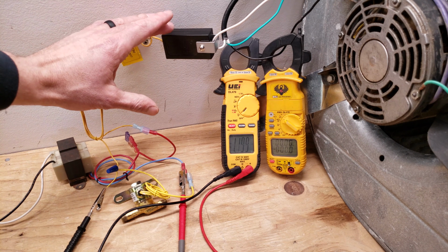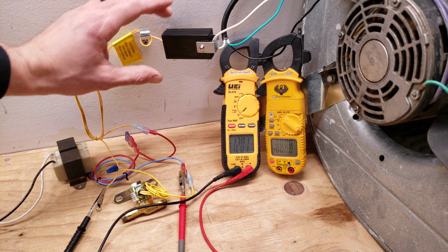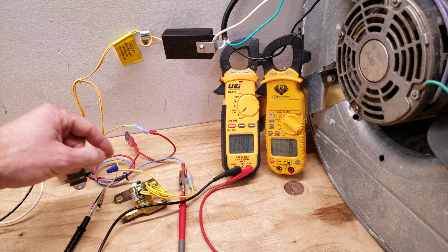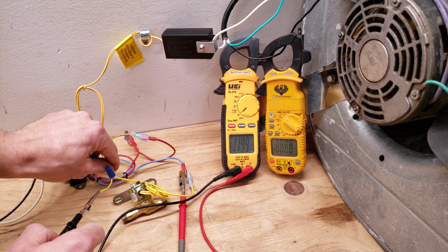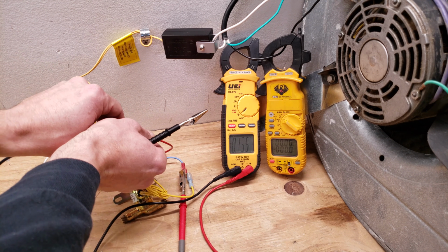So this current sensing relay is working properly, and it's not allowing the 24 volts to the solenoid, and I just want to show you that we are producing 24 volts at the transformer.